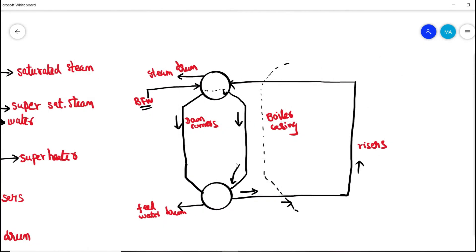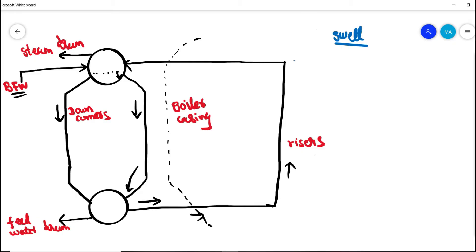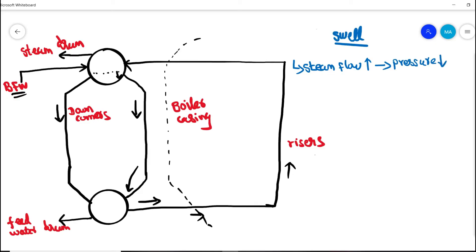This is the cross-sectional diagram of the boiler. Again, we have risers and downcomers. What is basically swelling? When steam flow increases, the pressure inside the steam drum reduces. When the pressure reduces, a different phenomenon occurs — the hot water and steam inside the riser bundle undergo flashing.